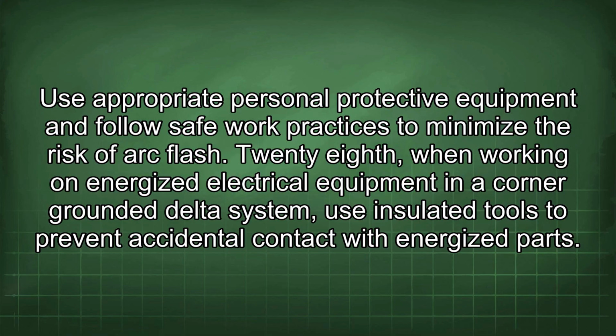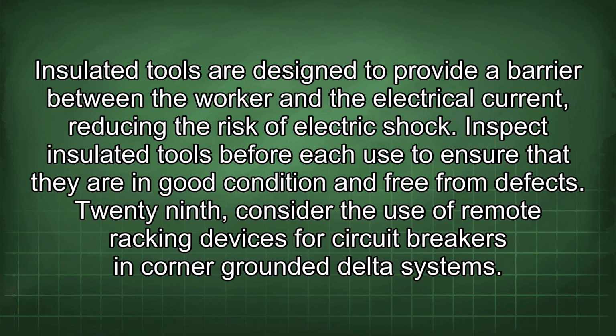28th, when working on energized electrical equipment in a corner-grounded delta system, use insulated tools to prevent accidental contact with energized parts. Insulated tools are designed to provide a barrier between the worker and the electrical current, reducing the risk of electric shock. Inspect insulated tools before each use to ensure that they are in good condition and free from defects. 29th, consider the use of remote racking devices for circuit breakers in corner-grounded delta systems.